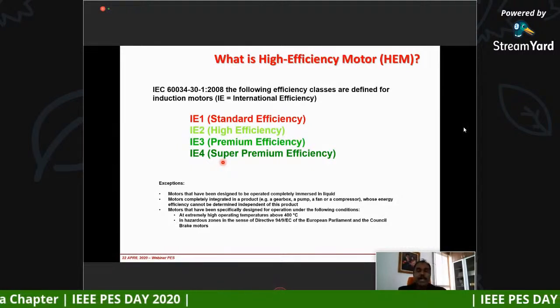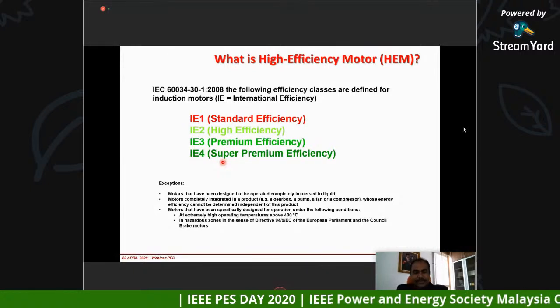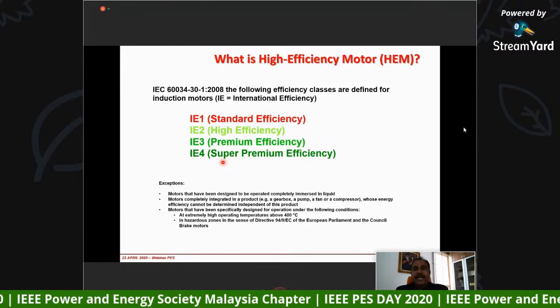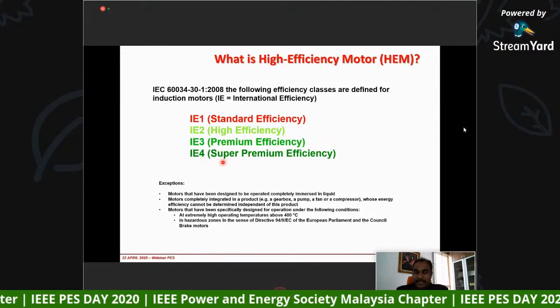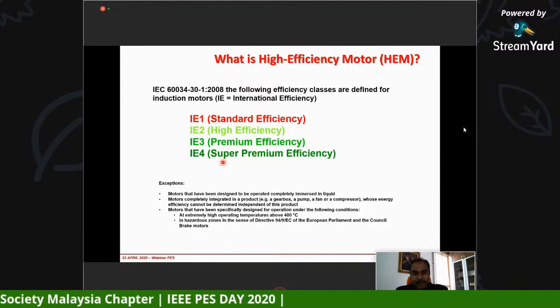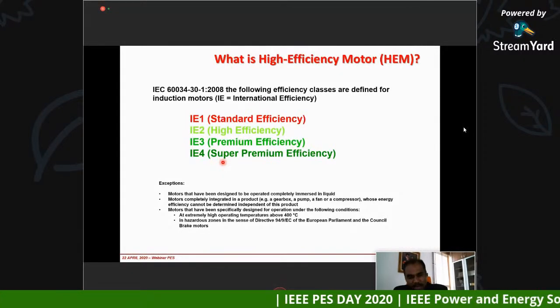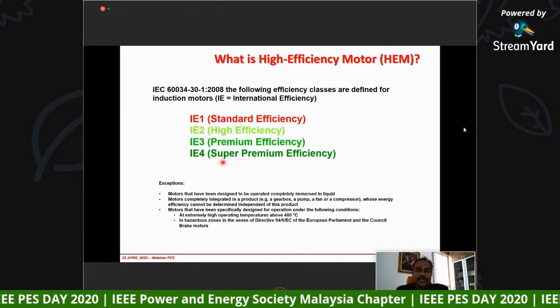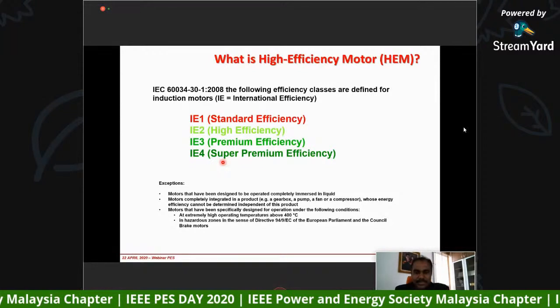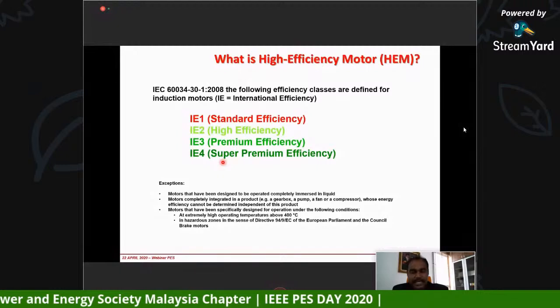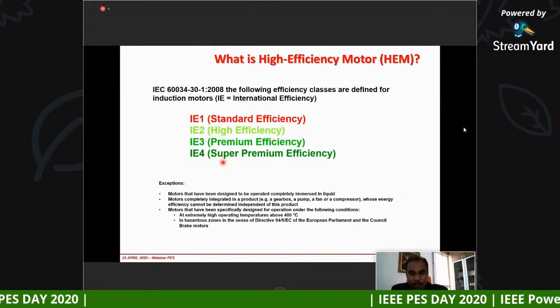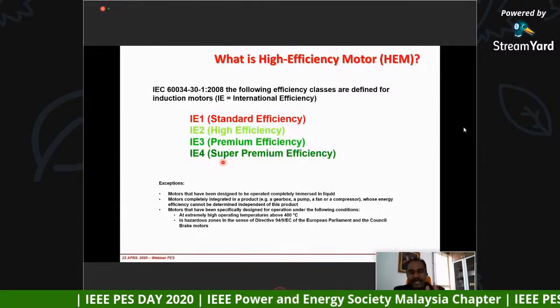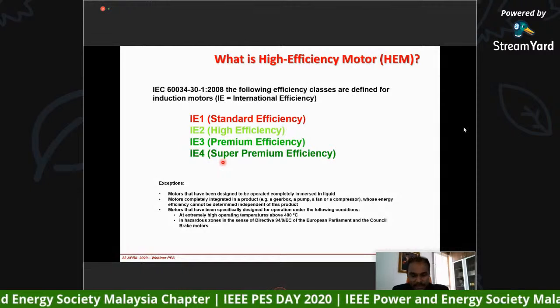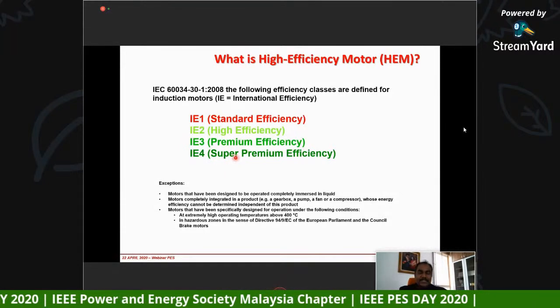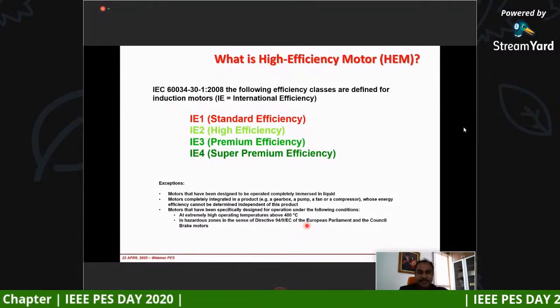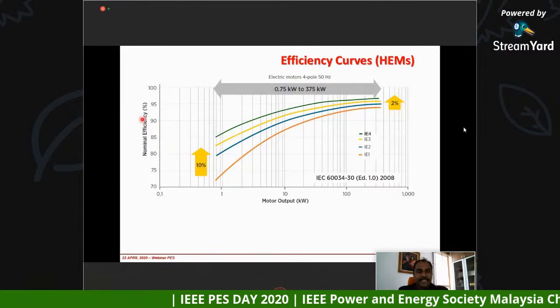For instance, if you buy a motor and then you connect that to a pump system, the motor could be an IE4 motor, which is a super premium efficiency, meaning it gives you high efficiency. But if the IE4 motor is connected to a pump system which is probably a low efficiency pump system, obviously the motor system efficiency is not going to be super premium. So the entire motor system efficiency should be lower. You cannot categorize it as IE4. So that's why when they categorize IE1, IE2, IE3, IE4, it's only referring to the motor alone. So that's the point that we have to understand. Okay, now move next. Now, again, in graph format, this is the efficiency and this is the power.